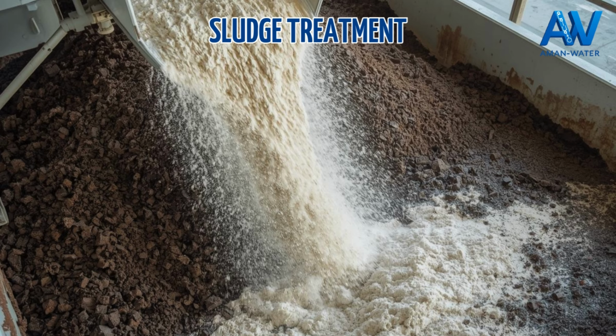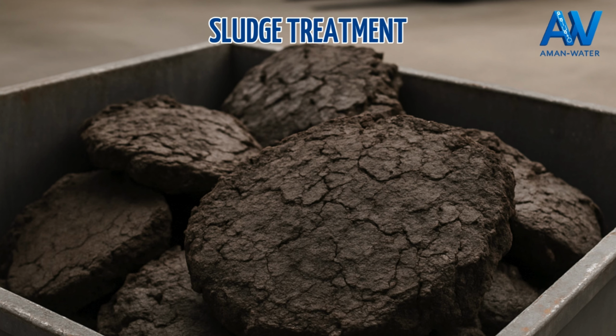Depending on the final destination of the sludge, hygienization may be required. This step eliminates remaining pathogenic germs. It can be achieved by heating, by adding lime, or through extended composting. Thermal or solar drying can then raise the dry solids content to more than 80%, or even 90%. The result is an almost completely dry sludge.